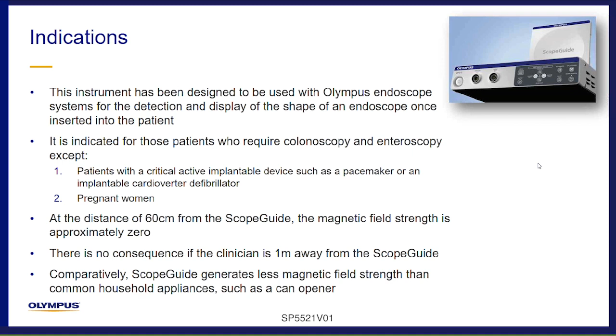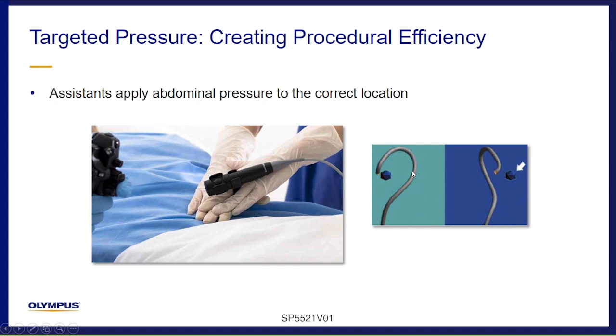Targeted pressure, creating that procedural efficiency that we touched on earlier. This is the hand coil that comes with the system. Your technician, your assistant can apply pressure to the patient's abdomen in the precise location that you see on your ScopeGuide that's looping. So once you identify the loop, you can actually have this hand coil on the abdomen, which is also picked up by the sensor, and apply the exact pressure where needed to avoid that loop. The next few slides will show you what I'm talking about in real time.